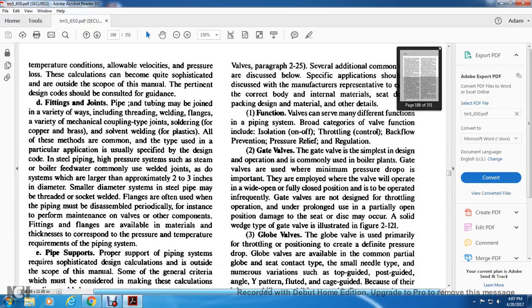Valves, paragraph 2-25. Several additional common types are discussed below. For special applications, consult manufacturer representatives to ensure the correct body and internal material, design, packing, and other details. One function: the valve can serve many different functions in the piping system. Broad categories of valve function include isolation (on-off), throttling, control, backflow prevention, pressure relief, and regulation.